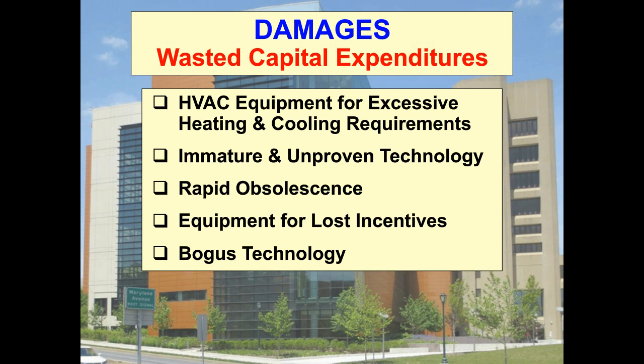Another type of wasted expenditure is for immature and unproven technology. Geothermal heat pumps are a common contemporary example. Typically this expenditure occurs because a designer, usually an engineer, recommends it to the client without giving responsible consideration to the shortcomings of the technology. In other words, the engineer is using the client as a guinea pig. We see too much of that.